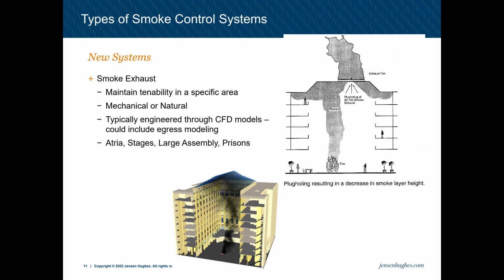And we also include prisons in here. Prisons also require smoke control systems for a different reason, is that in a prison, if there is a fire, the occupants, the prisoners themselves, are not capable of egressing the space on their own. They're not capable of a term called self-preservation. They require the assistance of the officers and the people in charge of the prison. So if there's a fire within the prison and it's a sleeping quarters, we have to make sure that those people can still be protected in those types of events.